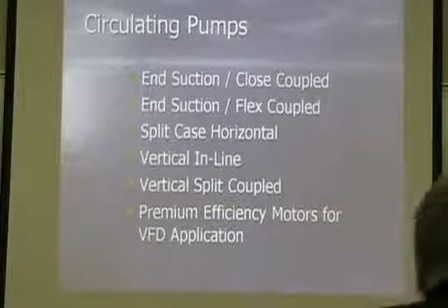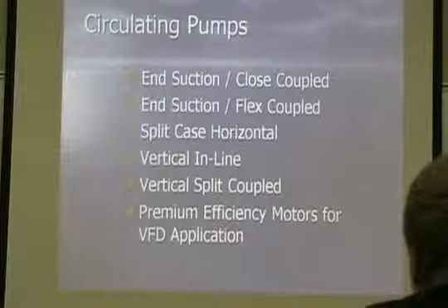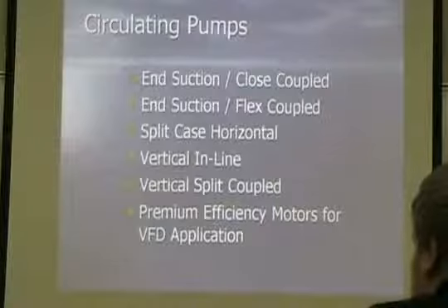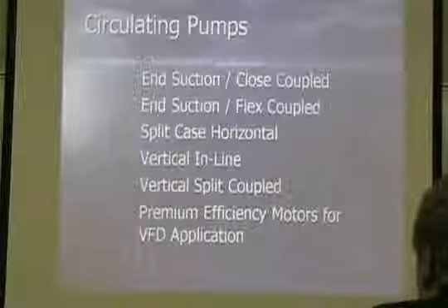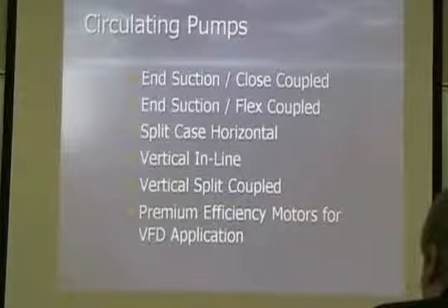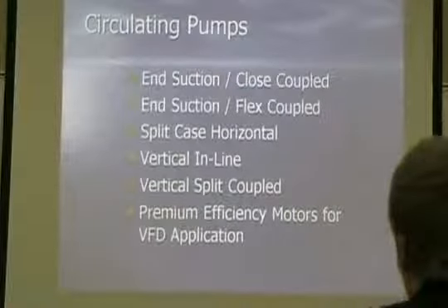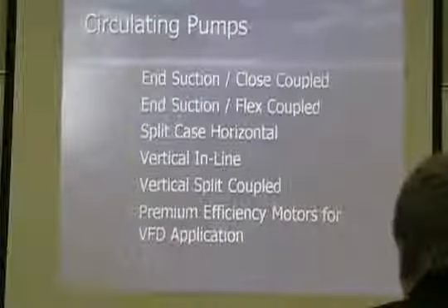What you have in the loop, let me go ahead and get to it. In a water source heat pump system, you're going to have a piping loop similar to most any other piping loop system, where I've got heat pumps and a circulating pump that circulates water out to the heat pumps and returns it back to a boiler or a cooling tower. And I've got some drawings that show that. But you will have a circulating pump in the system just like any other chilled water or heating water system. Most any kind of pump works.